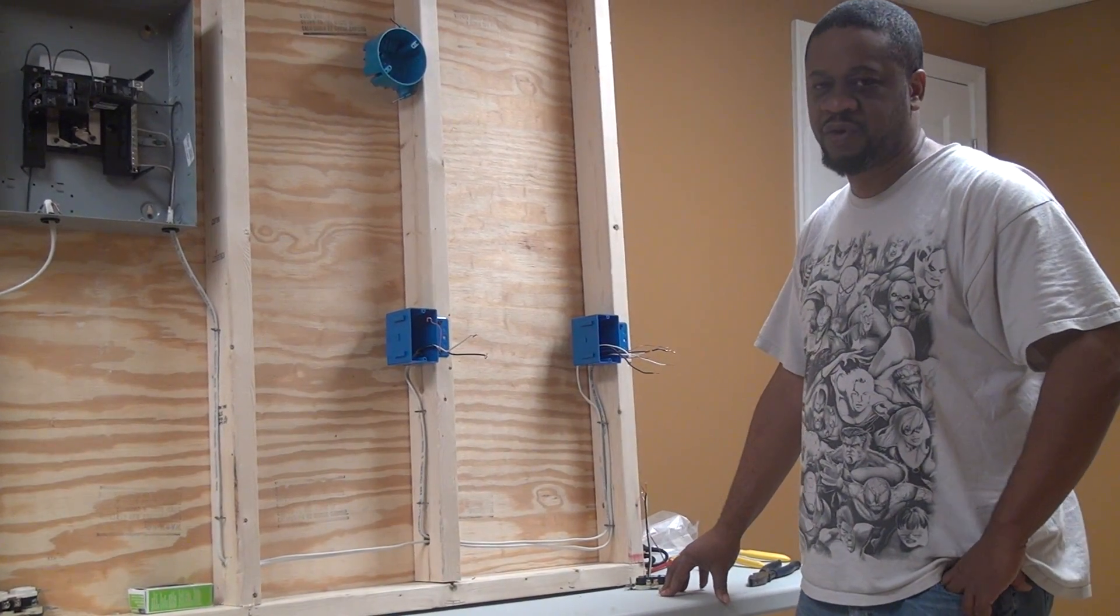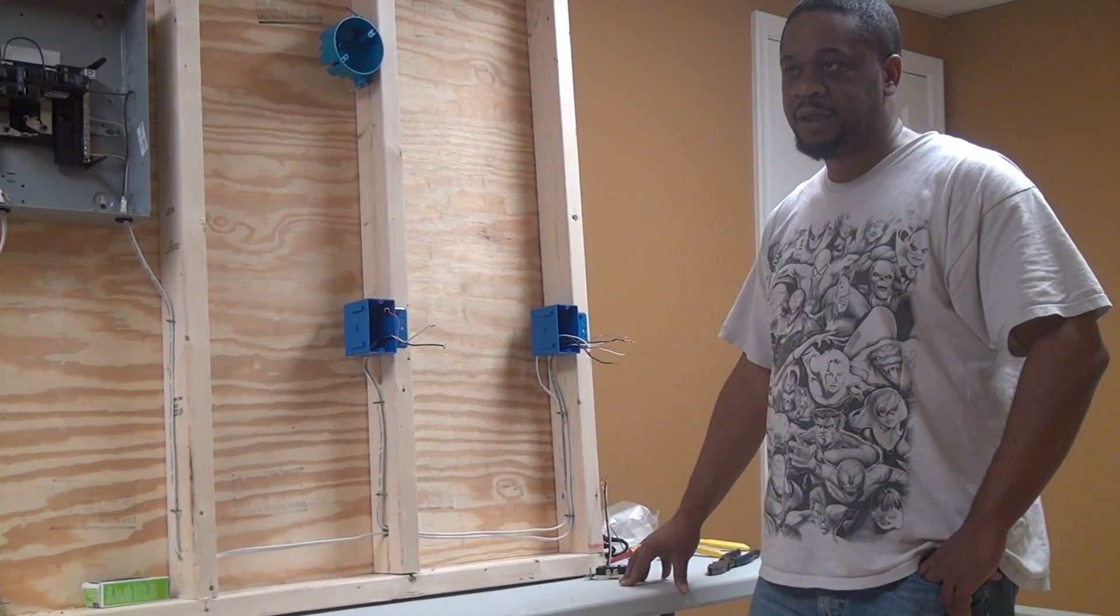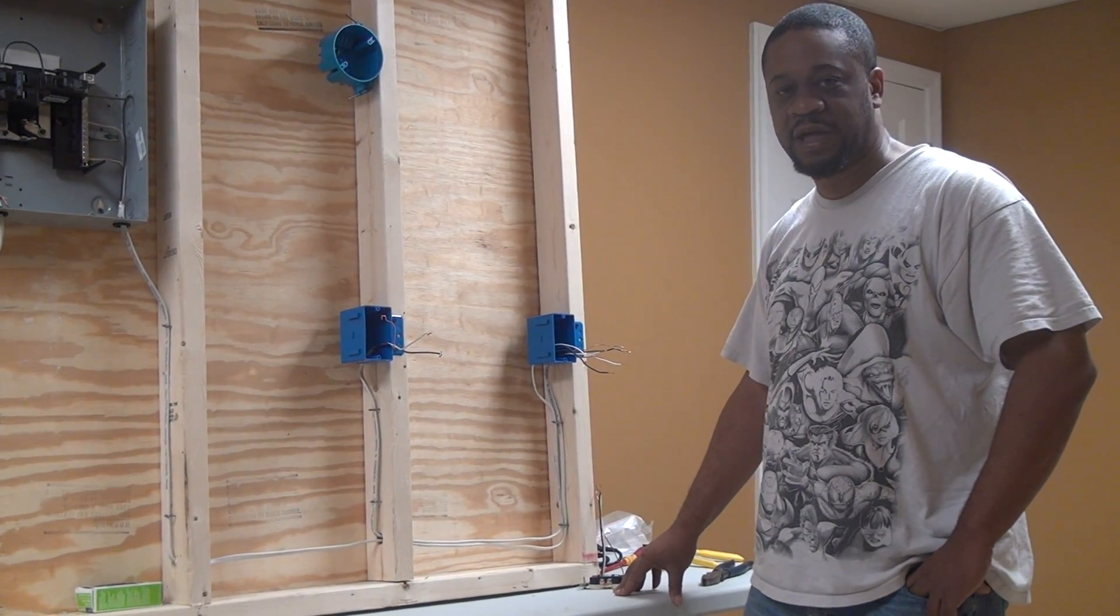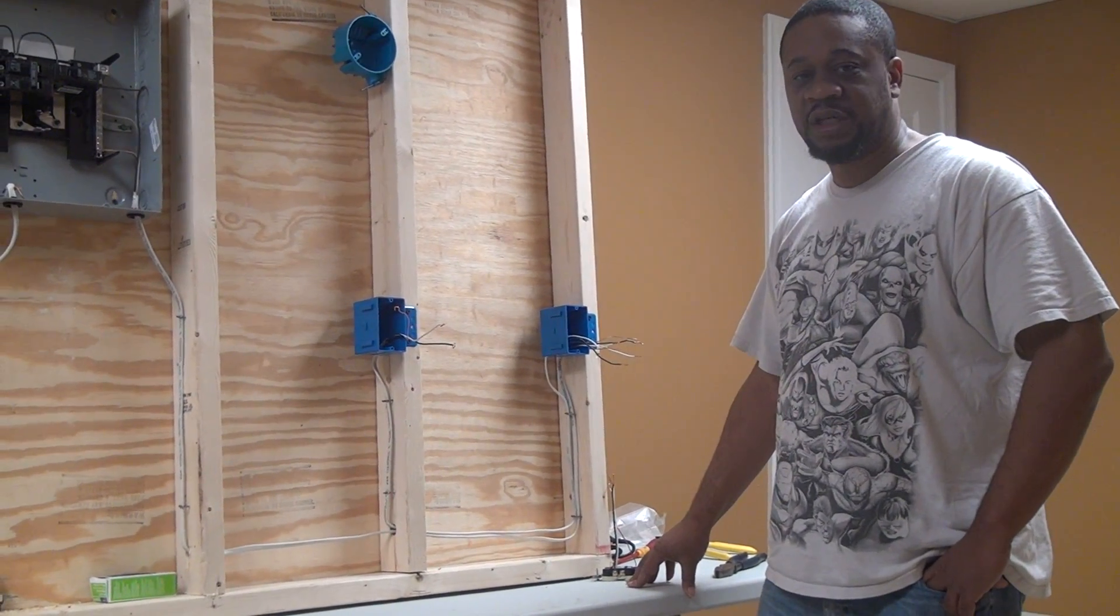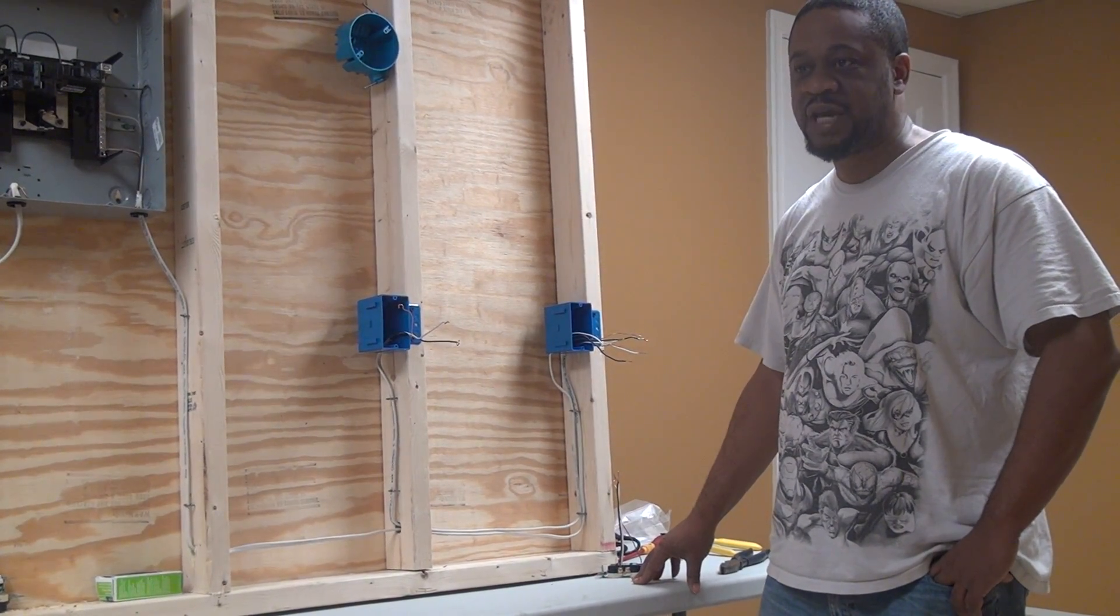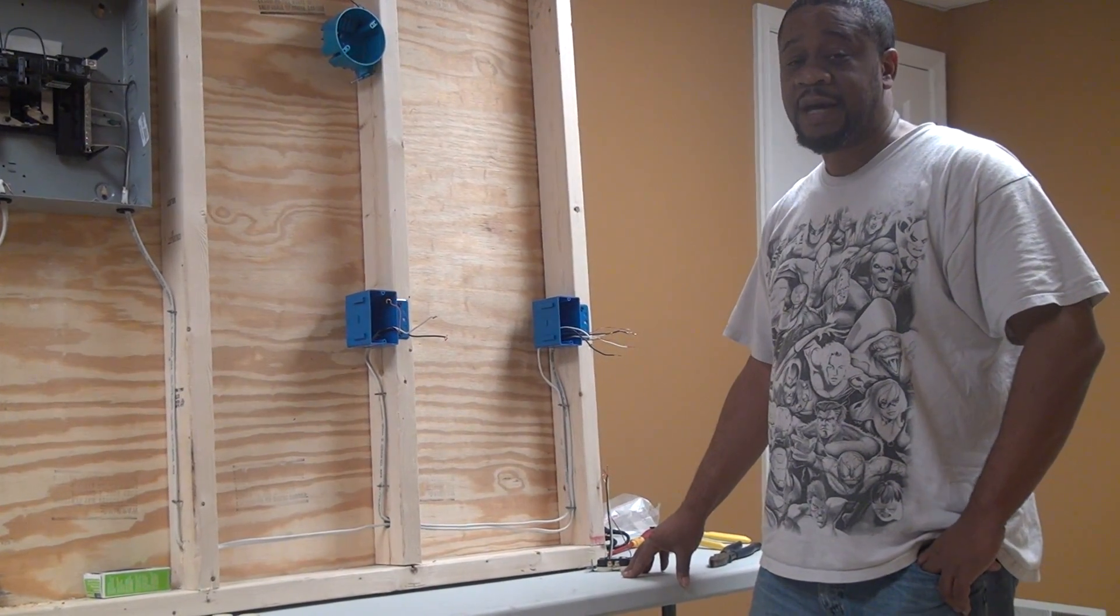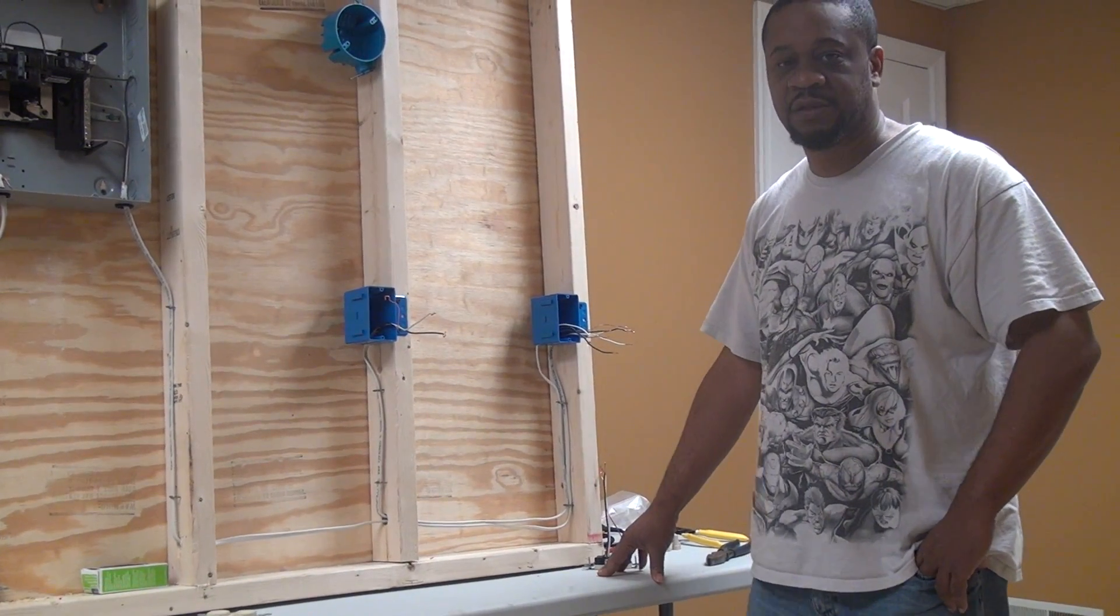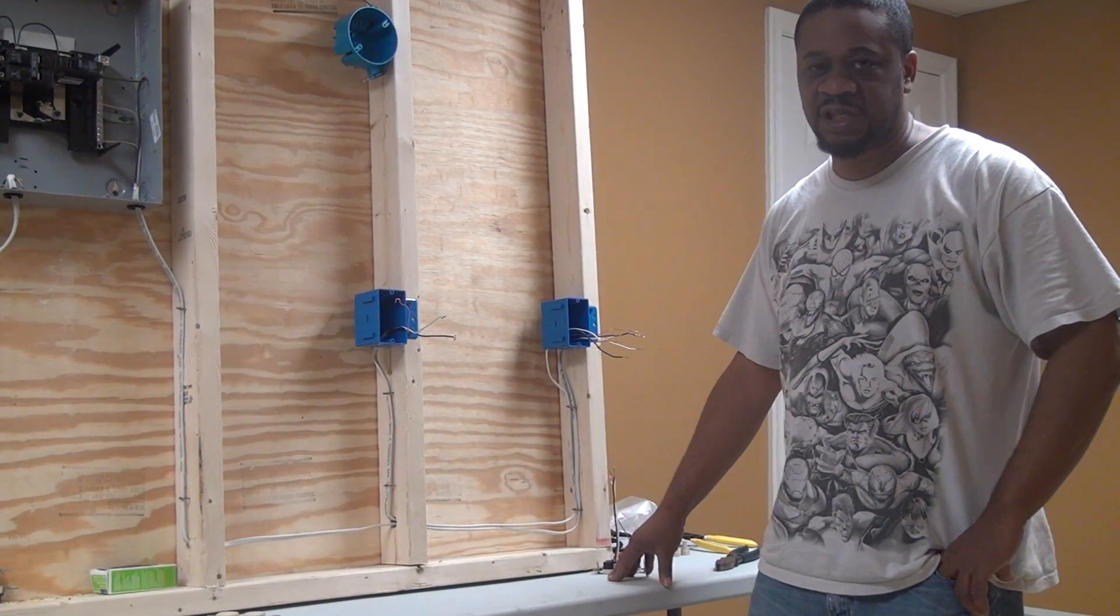The code also has a requirement for the number of outlets to be installed along a wall line. The code has a really bad way of telling you to space your outlets 12 feet apart. What it says is that when you measure anywhere horizontally along the wall line within six feet, you should have an outlet. All that means basically is put them 12 feet apart. I would suggest putting them a little closer together.